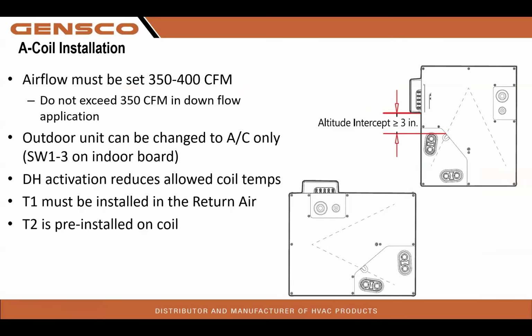Airflow must be set between 350 and 400 CFM on that gas furnace, guys. Do not exceed 350 in your downflow application, or we could have condensate liftoff of the coil. Outdoor unit can be changed to AC only. If we set SW1-3 on the indoor board, we can turn it into a straight AC, and that also goes for the air handler. T1 sensor, the return air sensor, must be installed into the return air, and T2 is pre-installed in the coil. So the only sensor you will need to install is the T1 sensor into the return air.